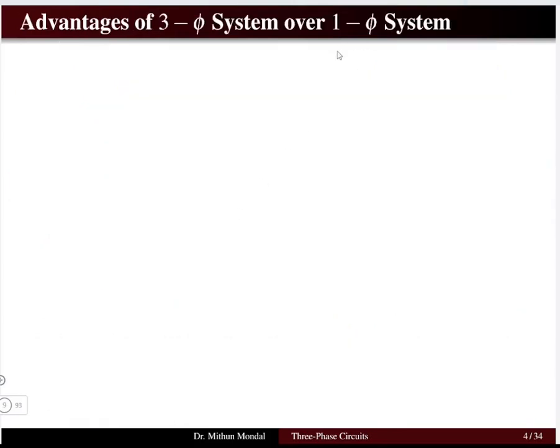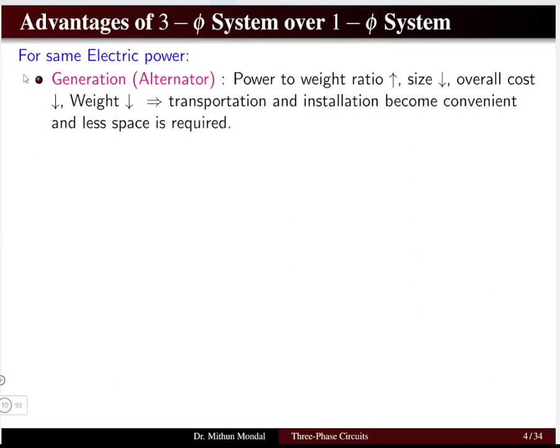Why are we moving from single-phase to three-phase systems? What are the advantages? All comparisons assume the power transmitted is equal whether single-phase or three-phase. On the generation side, when you use a three-phase synchronous generator or alternator, the power-to-weight ratio increases, meaning the size of the alternator decreases compared to a single-phase system transmitting the same power.